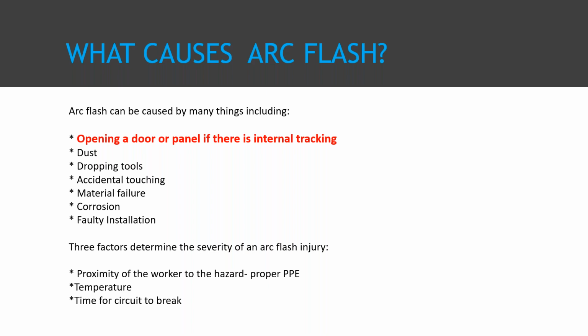That can help you from a burn standpoint. It can't always help you from getting thrown against a wall from the actual explosion, but at least it can help you from the burn standpoint. The other thing is the temperature, and the last is the time for the circuit to break and for the arc flash to be over. So how long does it actually last?